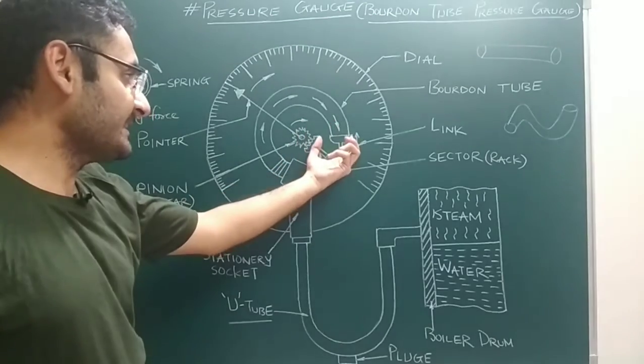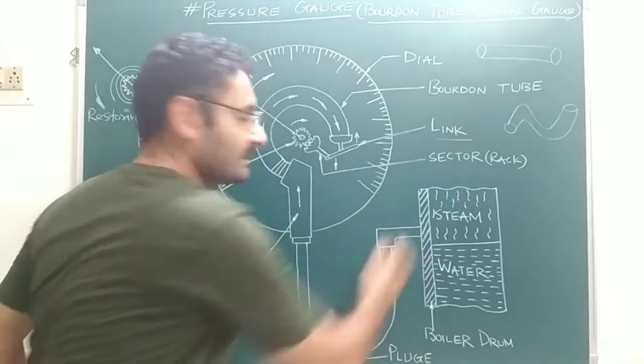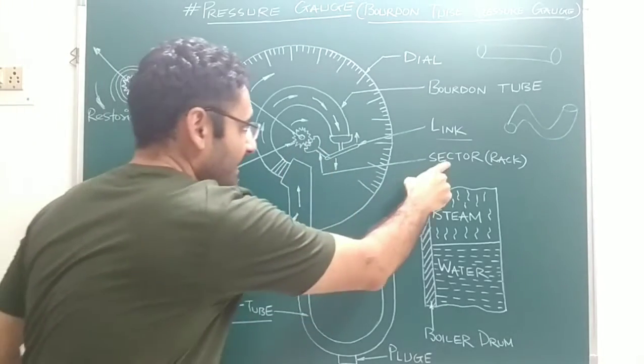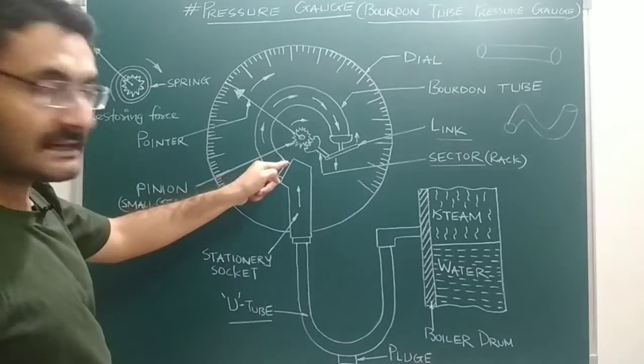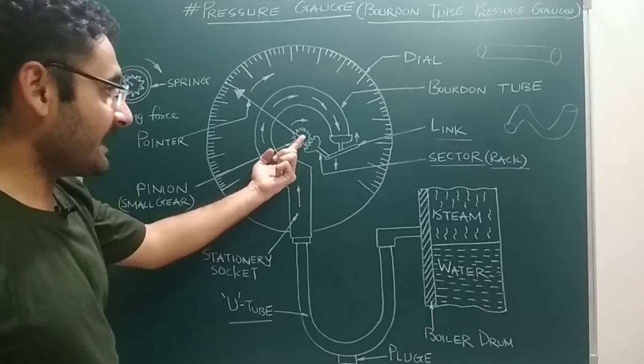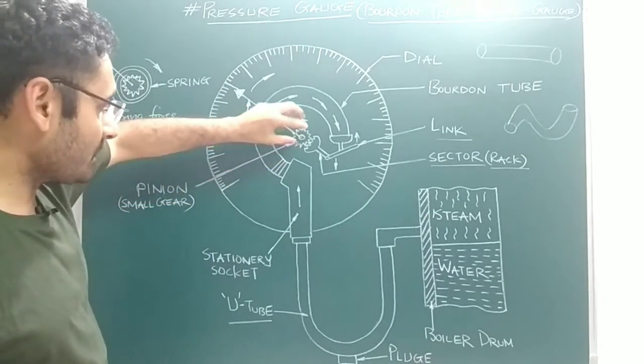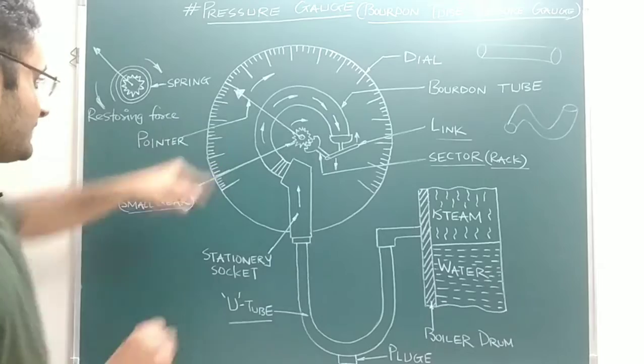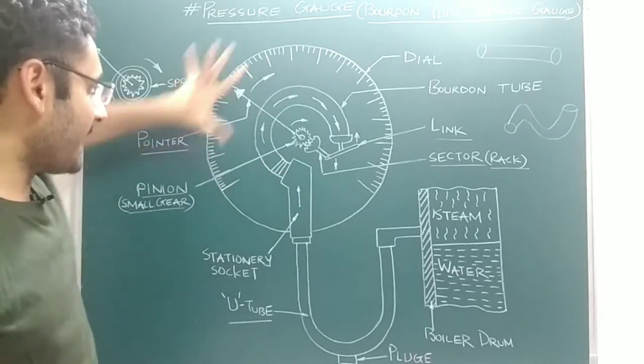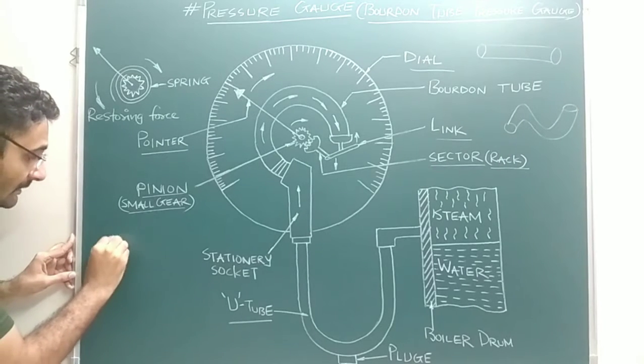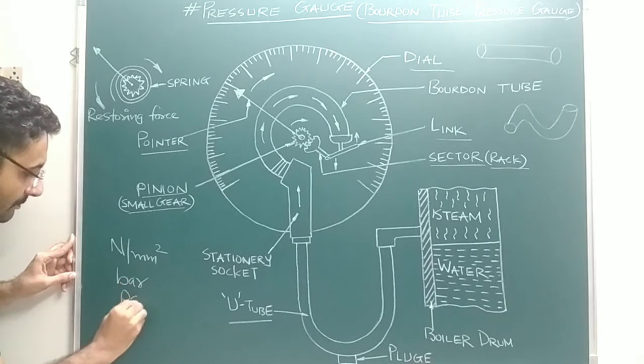The Bourdon tube is connected with one link. That link can move in the upward as well as downward direction. The link is connected with one sector. On one side of the sector some teeth are constructed, so that sector acts as a rack — like a rack and pinion. That rack is connected with one small gear, also with teeth, known as the pinion. The pinion is connected with a pointer, which is located on a dial with pressure markings in N/mm², bar, or pascal.